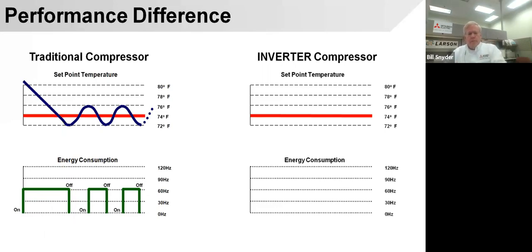It opens up, drops out the compressor, and we'll coast for a while until we raise the temperature above set point, and we get this on-off contactor compressor running on-off. And the temperature, although this is exaggerated, between 72 and 76, it's not uncommon to fluctuate 1 degree above and below the line, just trying to maintain a set point. As long as this contactor is pulled in and the compressor's on, the evaporator should be cold and below the dew point and drawing humidity out of the air, which in some of our areas is extremely desirable to keep the humidity low. And that's the way a conventional system works.